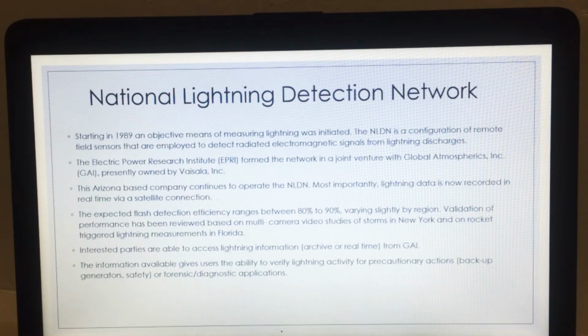National Lightning Detection Network. Starting in 1989, an objective means of measuring lightning was initiated. The NLDN, also known as the National Lightning Detection Network, is a configuration of remote field sensors that are employed to detect radiated electromagnetic signals from lightning discharges. The Electric Power Research Institute, EPRI, formed the network in a joint venture with Global Atmospherics (GAI), presently owned by Vaisala Inc. This Arizona-based company continues to operate the NLDN. Most importantly, lightning data is now recorded in real time via a satellite connection.